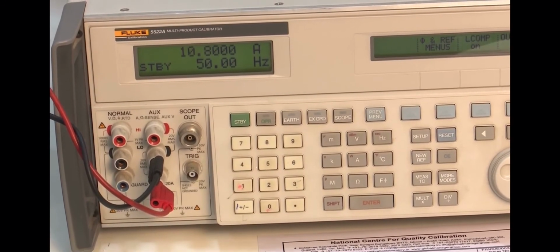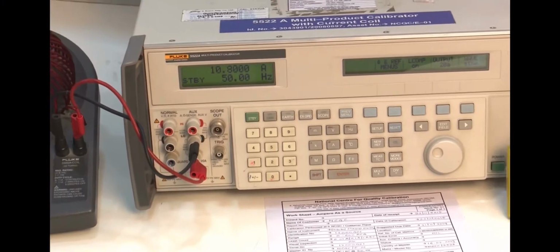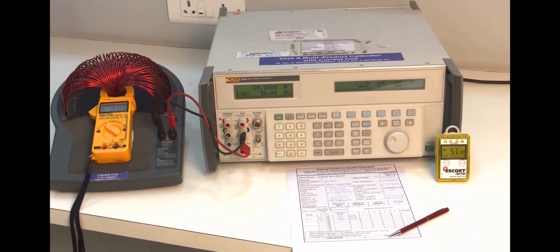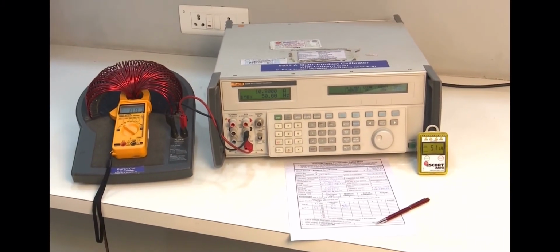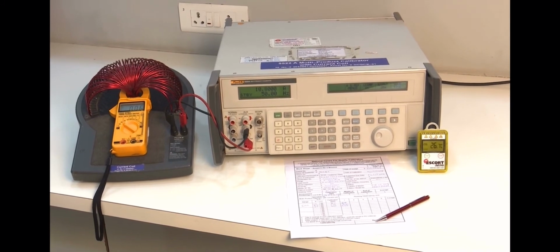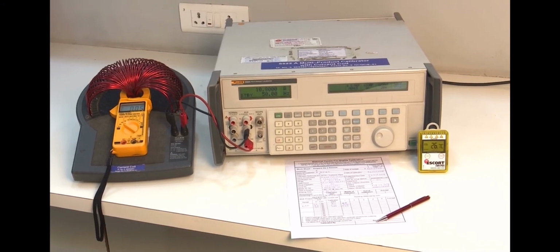In this way, the demonstration of calibration of digital clamp meter for 3 calibration points is completed for training purpose. You have to repeat the steps shown here for 4 times to complete calibration of this particular range. Similarly, we can calibrate the clamp meter for ampere, volt, resistance and frequency range.